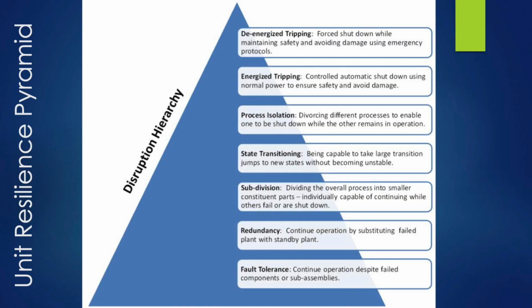So there's a disruption hierarchy, a pyramid, that we implement at all modern power stations nowadays. At the very foundation of it is fault tolerance - in other words, you try to design the plant to be as resilient as possible. It should not fall over if the voltage goes out of its band a bit, or when the frequency goes out a bit. The second layer in this pyramid has to do with redundancy.